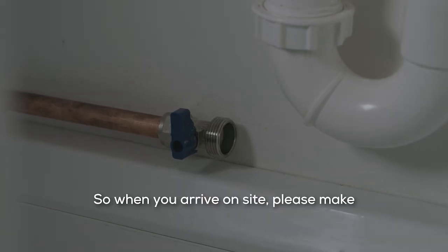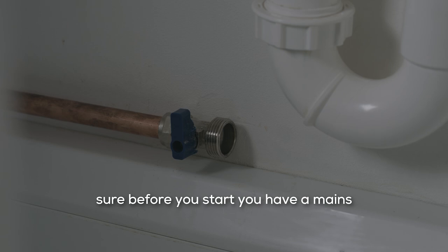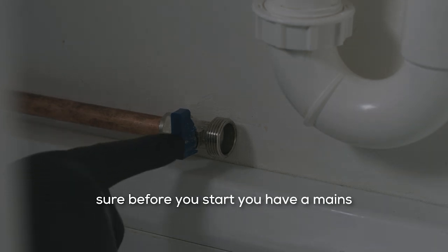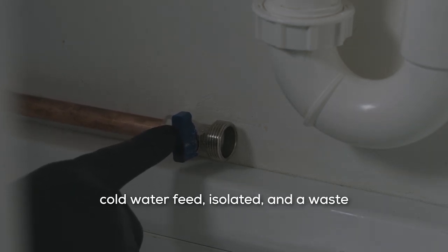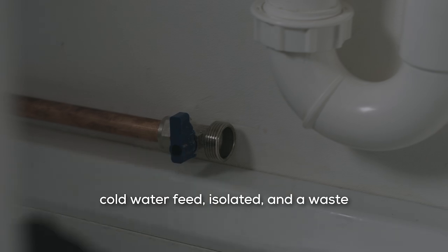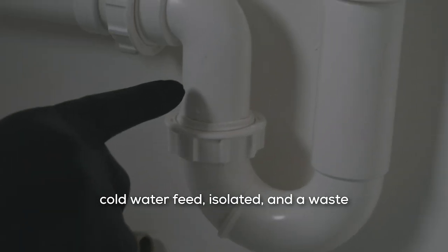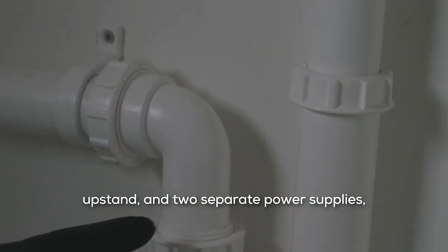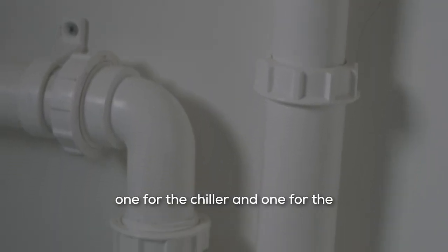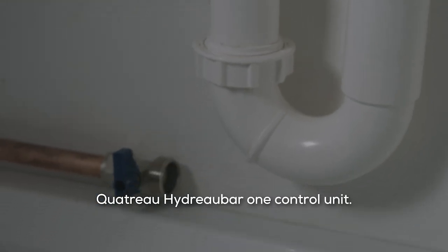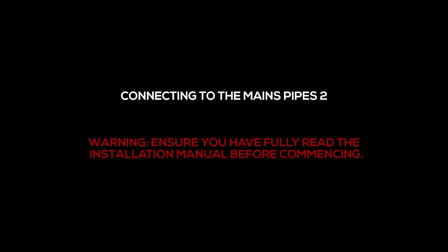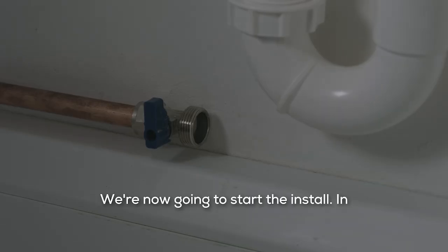So when you arrive on site, please make sure before you start you have a mains cold water feed isolated and a waste upstand and 2 separate power supplies, one for the chiller and one for the HydreauBar 1 control unit. We're now going to start the install.